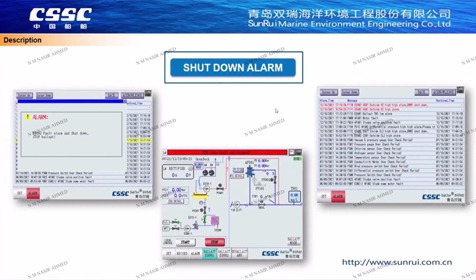First of all, we need to know the alarm of a Sunrui BWMS is divided into two types. First one is shutdown alarm. All shutdown alarms will indicate a pop-up window of the EDU fault. Like this picture, when the shutdown alarm happened, the information bar at the top of the screen will display the red and indicate EDU fault.